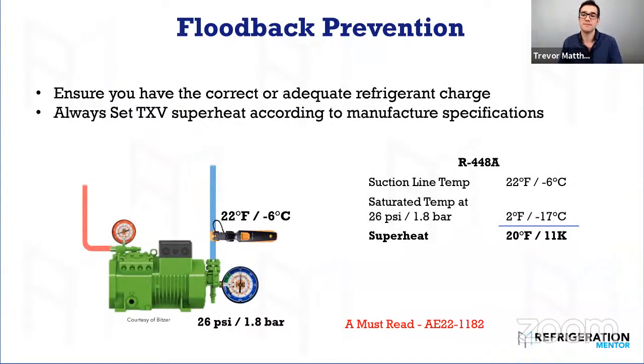Floodback prevention. Set the superheat properly accordingly. You need to check the Bitzer manual. You need to check the Copeland manual, see what they say. They're a little bit different, but not by much. I always say 20F or 11K back to the compressor. That's enough cooling. You're not overheating. You're not flooding. Could it be 15 Fahrenheit or 9K? Sure, it could be, as long as you check it at every load, every condition, that it's not flooding back at all. And then CO2 compressors are totally different as well.